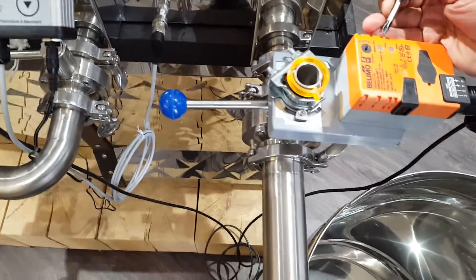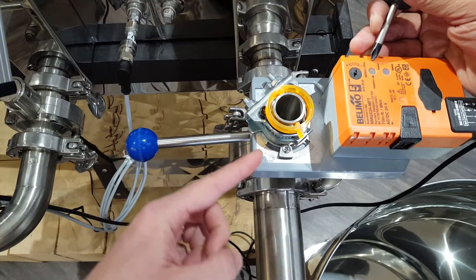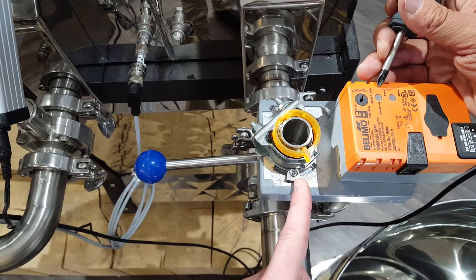The only thing is, we need to tell the motor that we did that, because if we don't, the motor is still going to try to fully open. But when it hits that little stopper, it might damage the motor.